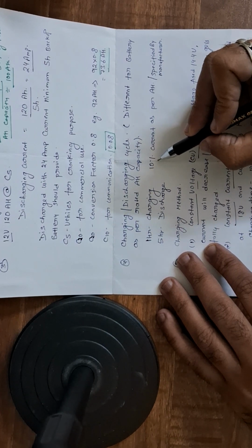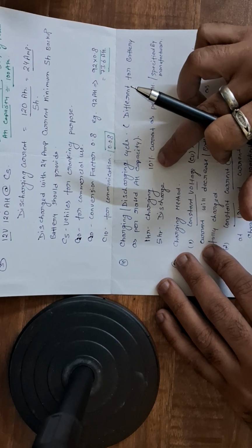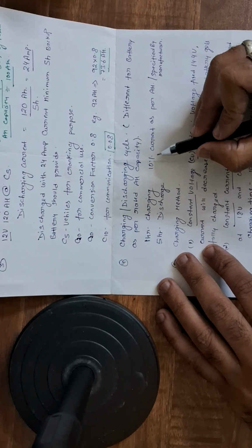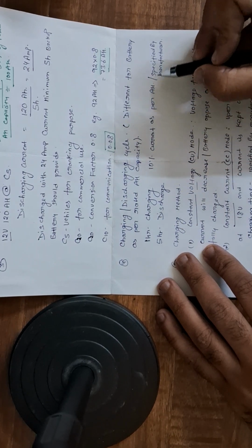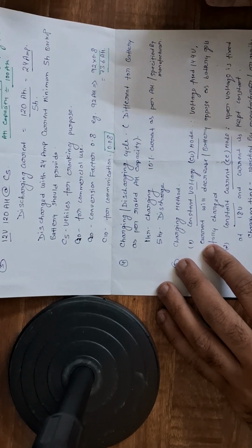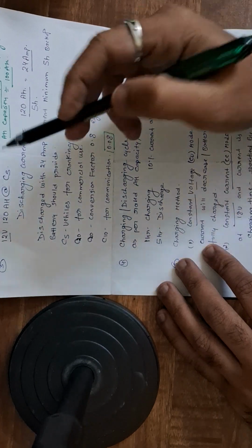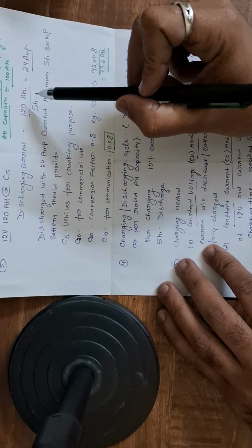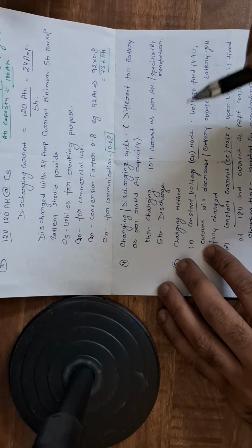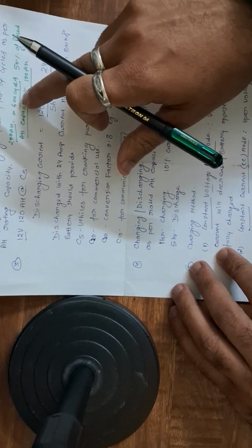And generally, the charging current is specified by the manufacturer, but if it is not specified, then we have to take 10% of the rated Ah capacity as the standard. Otherwise you can take 10% of the battery capacity: when we have a 120 Ah battery, if you don't know, for charging current you can take 12 ampere for charging this battery. Since this has 600 cycles, this is an example.